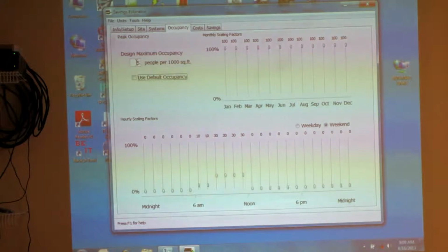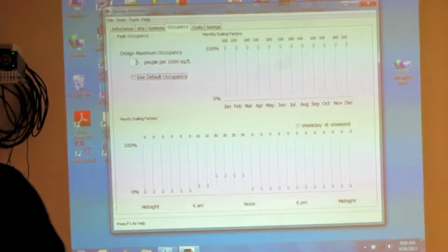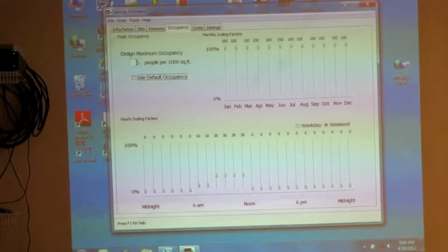You know, if you go up on the roof and the dampers are closed and you see through them, chances are you've got to replace those dampers because you're heating the great outdoors. So that's just a neat tool. It's been around a long time. We've had different versions of this for years. Once again, on a green building, this is the way to do it.